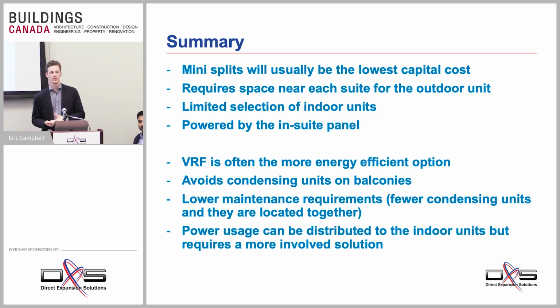Lower maintenance requirements, again, because it's not on a balcony and VRF is instead centralized on the roof, and you might have two condensing units instead of 20 mini split condensing units. There are savings on the maintenance side. You don't need to enter someone's suite to do that regular maintenance. Instead, it's in a space on the roof that has access for the qualified maintenance personnel.